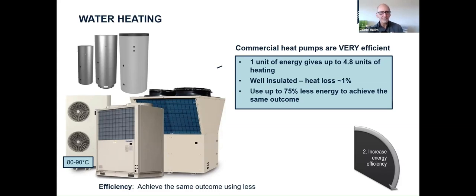Now, the difference between them and the traditional way is for every unit of energy we use on a heat pump, we get nearly 5 times the amount of water heating than we do with the traditional one. So remember, with the traditional unit, for every unit of energy, we got almost 1 unit of heating. Yet for a heat pump, you get 5 times more.